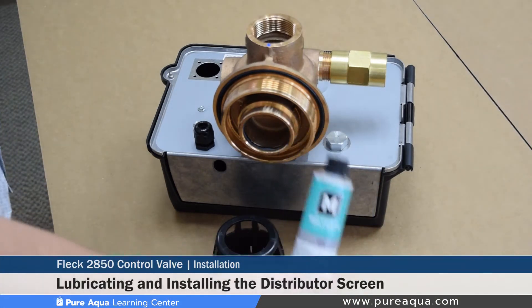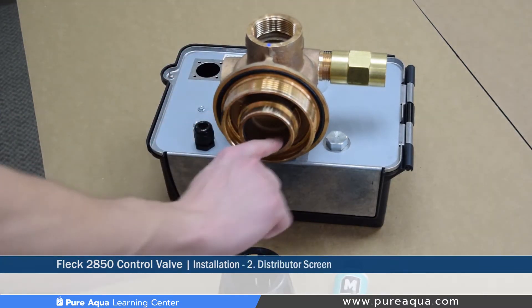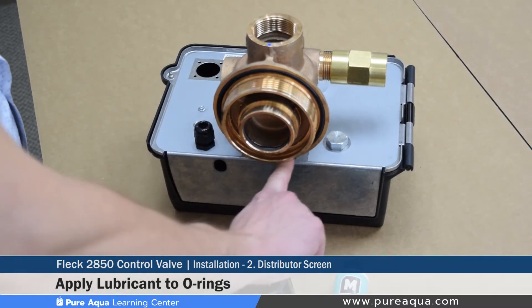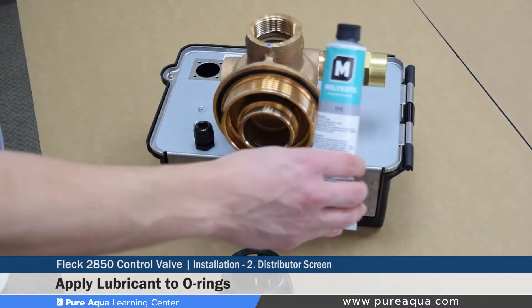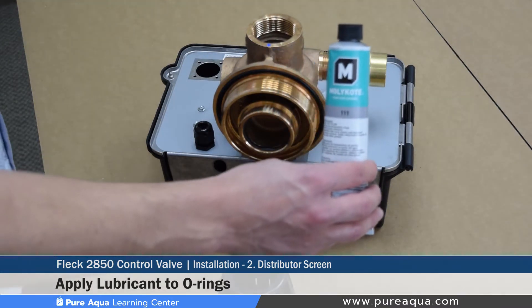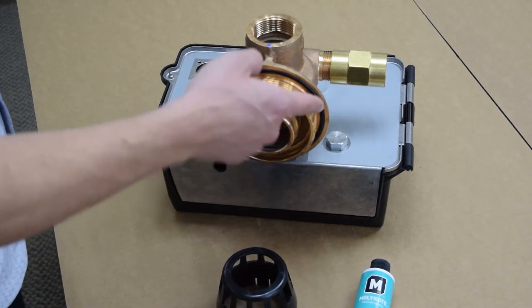Step two of the installation procedure is to lubricate the two o-rings on the valve body and install the distributor cone. The two o-rings that need to be lubricated are the inner o-ring and the outer o-ring, which seals the tank and valve. The recommended lubricant is the Molykote 111, which is an excellent lubricant used at Pure Aqua for various o-rings.